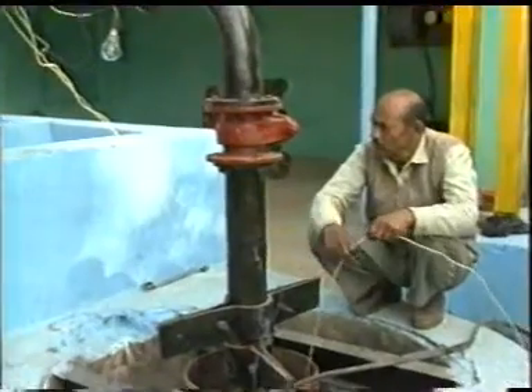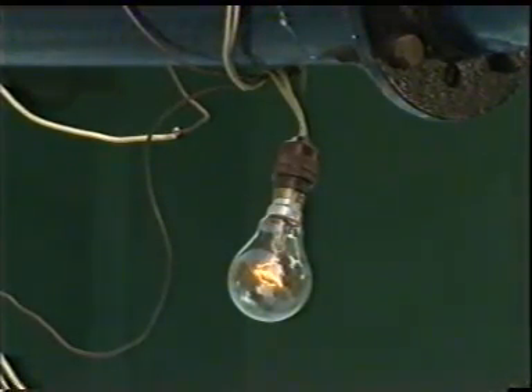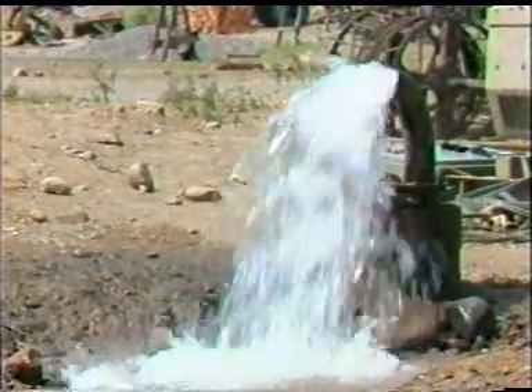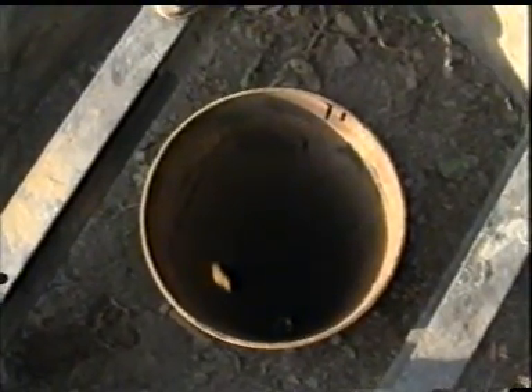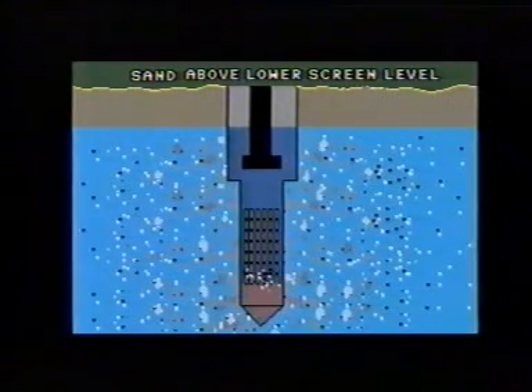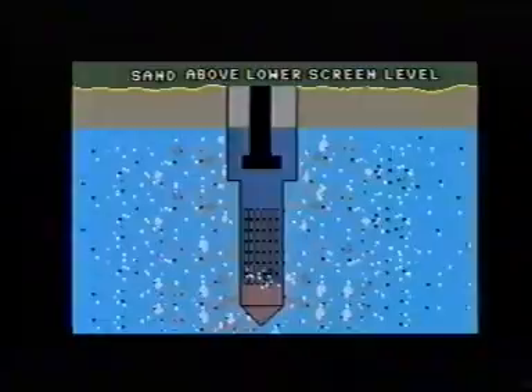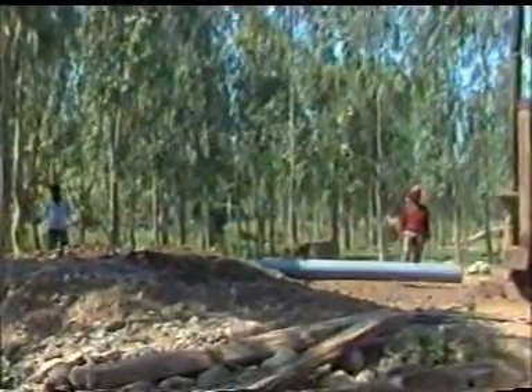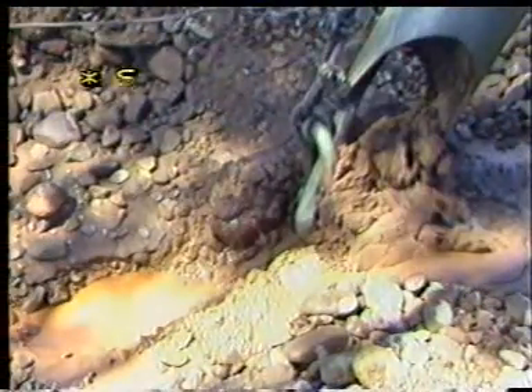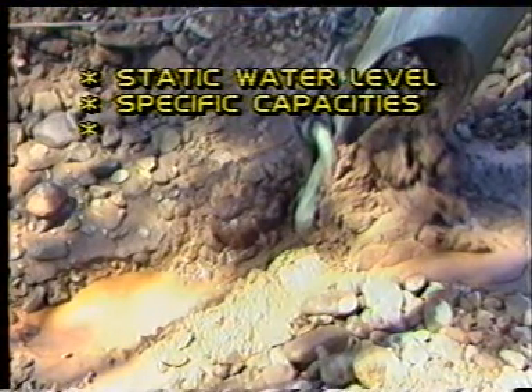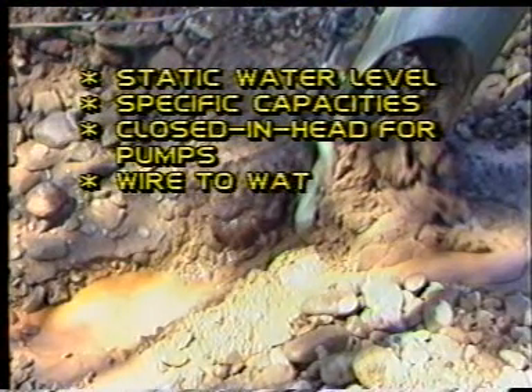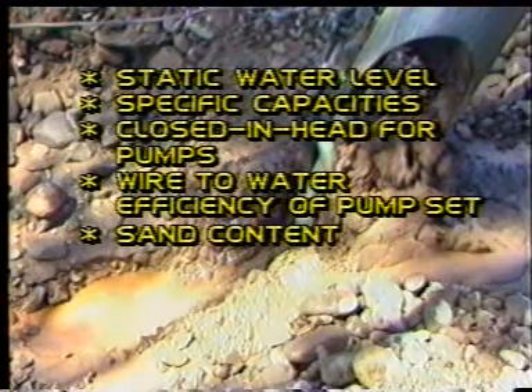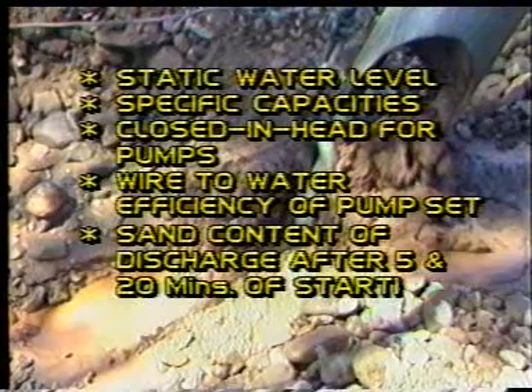For routine maintenance of a well, discharge and drawdown should be measured and recorded regularly. After each pumping season, total depth of water should be measured. In case sand gets accumulated up to a point in the well where it enters into the screen, this should be bailed out and cleaned before taking measurements of static water level, specific capacities, closed in head for pumps, wire to water efficiency of pump set, sand content of discharge after 5 minutes and 20 minutes of starting the pump, and chemical and bacteriological analysis of water samples.